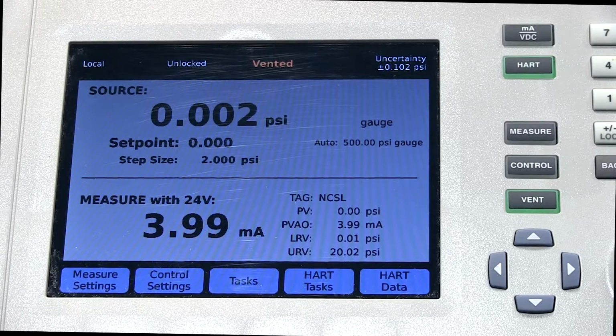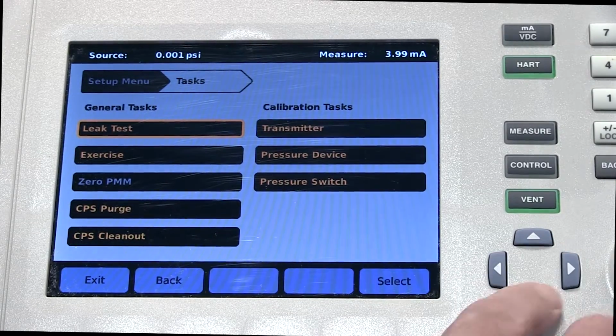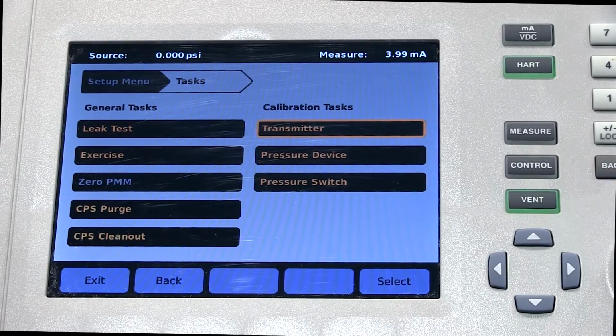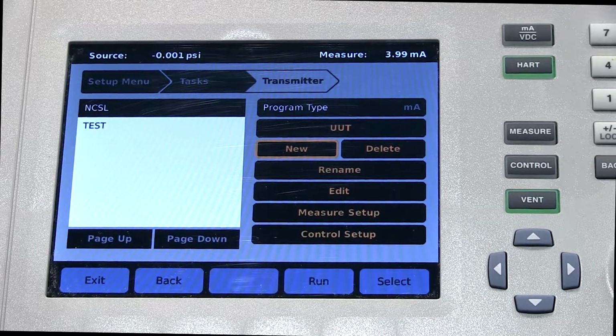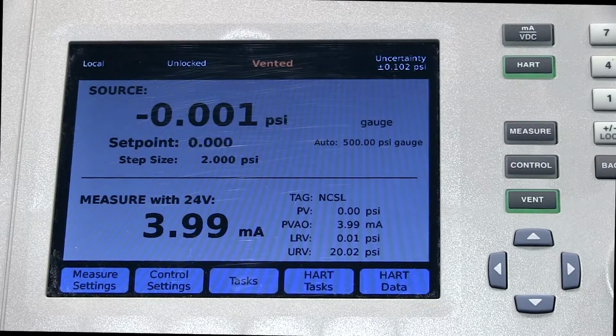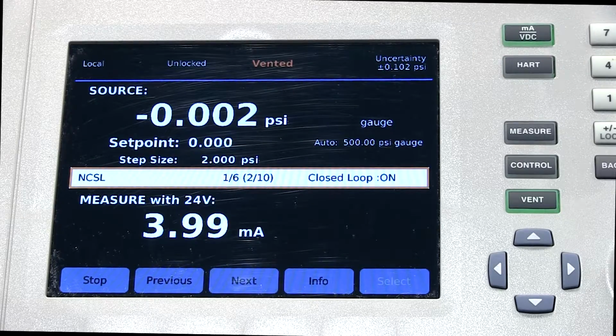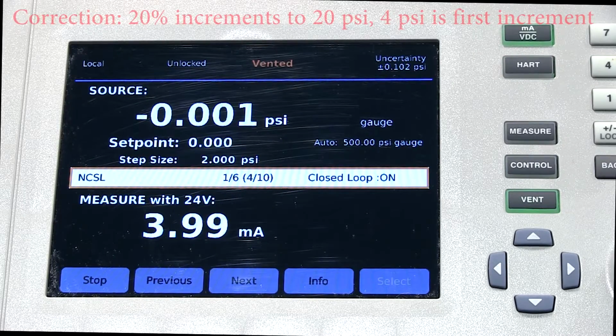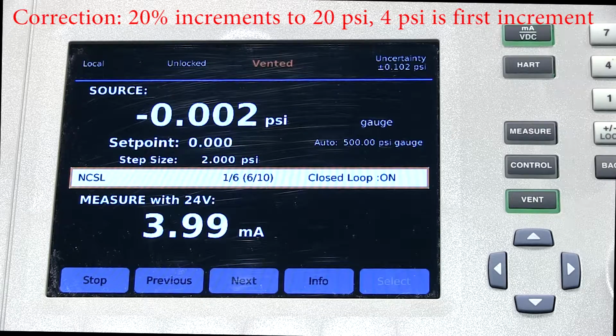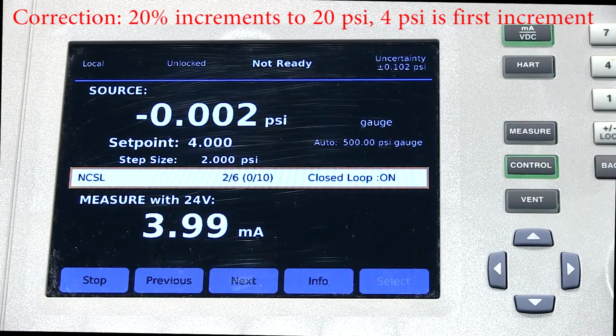If you are communicating with either HART or 4 to 20 milliamps or voltage, you can run pre-programmed tasks, fully automated task routines, like this one called NCSL. And this will ramp, I think this goes in 25% increments from 0 to 20 psi. Captures the value of both the reference and the unit under test.